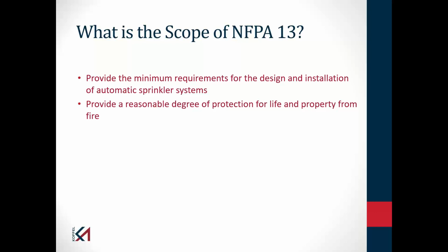And this first found its way into the codes back in 1991, when the Life Safety Code put in a mandate that all new sprinkler systems in healthcare occupancies needed to be what was called a quick response sprinkler, a type of fast response sprinkler. Now, prior to that, in residential occupancies, there clearly was the use of residential sprinklers, which is another type of fast response sprinkler. The advantage of the fast response sprinkler is that it operates more quickly, and it's not due to temperature rating, because I can get an intermediate temperature fast response sprinkler. It's due to the operating element itself. It will respond to that increase in heat more quickly than a standard response sprinkler will.